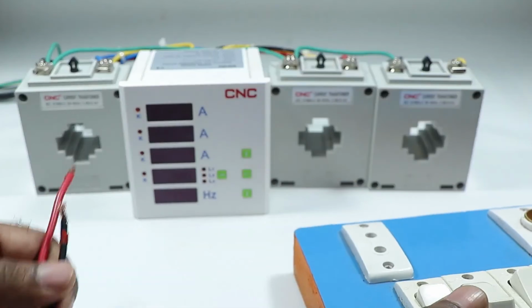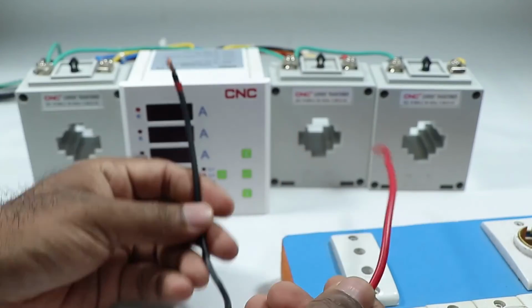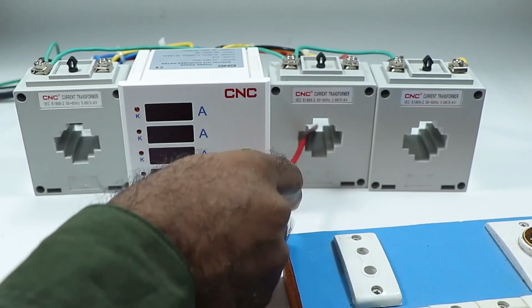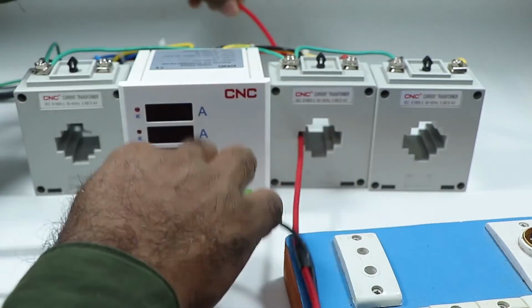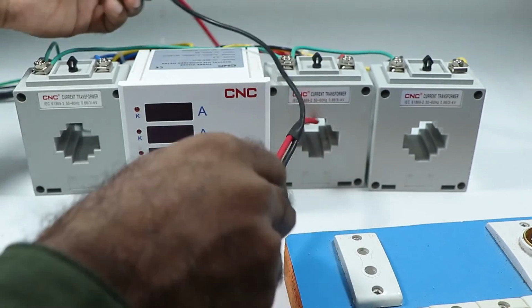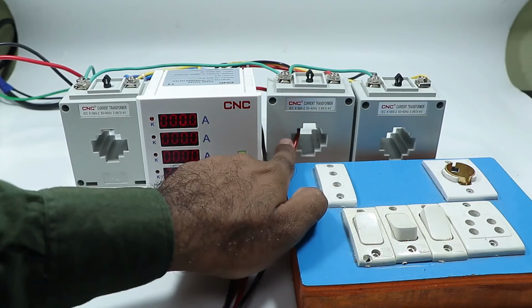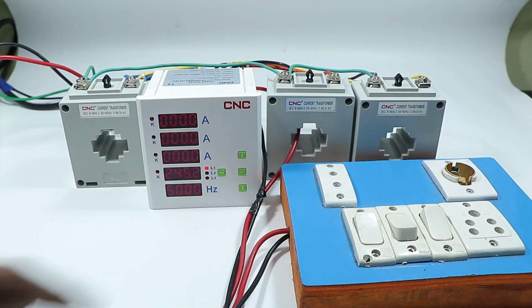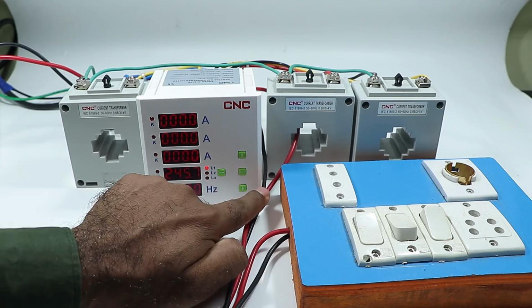In this switchboard I have taken the wire. Among these two wires, take the phase supply wire and pass it inside the CT. After this, connect this wire with the power supply. Friends, only the phase supply wire should pass inside the CT — the neutral supply wire must not pass inside it. I have the drill machine here.